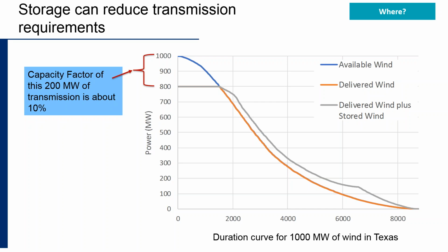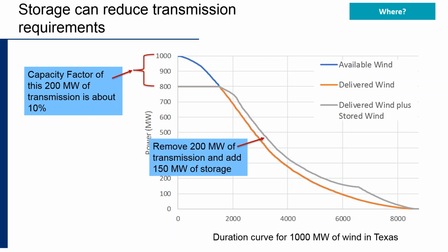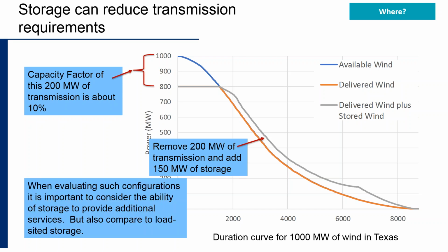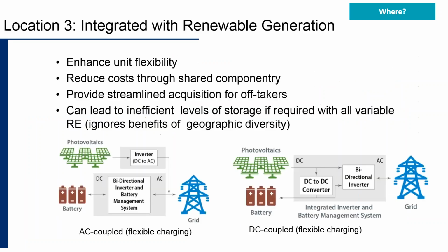Maybe it would be better to downsize the transmission, or oversize the wind relative to it, storing the wind when it exceeds transmission capacity and discharging it later. The gray line shows this use of storing wind—about 150 megawatts of storage added to 1,000 megawatts of wind, storing it and shifting it to a later time. This removes the need to oversize transmission relative to the wind, storing power for later, which increases the cost effectiveness of transmission. When considering this configuration, we always have to compare storage at this location to other locations, like load-sited storage. But this might be one application of energy storage that helps integrate more wind energy alongside providing peaking capacity and other services.